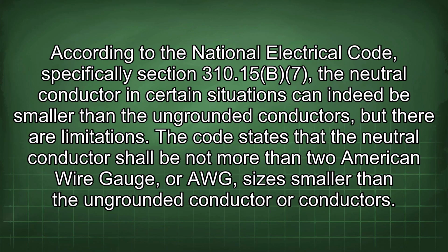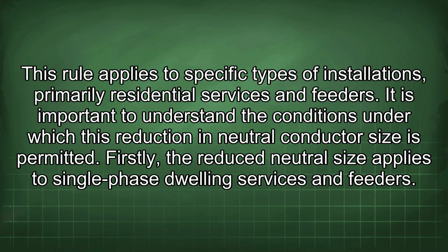According to the National Electrical Code, specifically Section 310.15(B)(7), the neutral conductor in certain situations can indeed be smaller than the ungrounded conductors, but there are limitations. The code states that the neutral conductor shall be not more than 2 American Wire Gauge, or AWG, sizes smaller than the ungrounded conductor or conductors. This rule applies to specific types of installations, primarily residential services and feeders. It is important to understand the conditions under which this reduction in neutral conductor size is permitted.